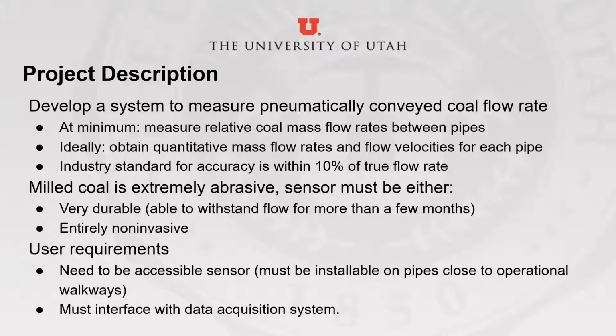So we are tasked to develop a system that can measure at least the relative coal flow rate between pipes, and ideally to give a quantitative mass flow rate for each pipe. The problem is that milled coal is extremely abrasive, so our sensor needs to be either very durable or entirely non-invasive, meaning it doesn't come into contact with the coal.